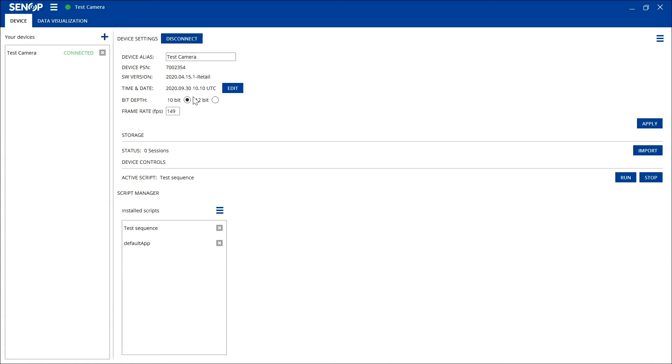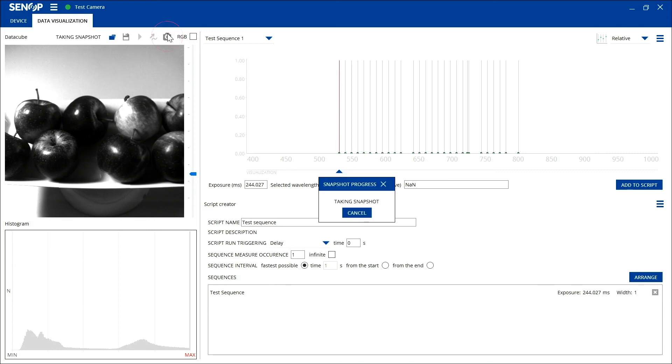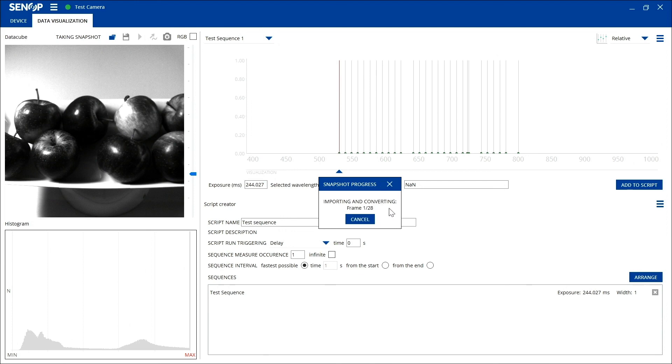The snapshot function on the HSI 2 software enables the user to measure one sequence and see the spectrum of the image. Go to the data visualization tab to take a snapshot with a defined sequence. Click the record button. The camera will now take the desired frames as defined in your sequence. A status window shows when the measurement is done.